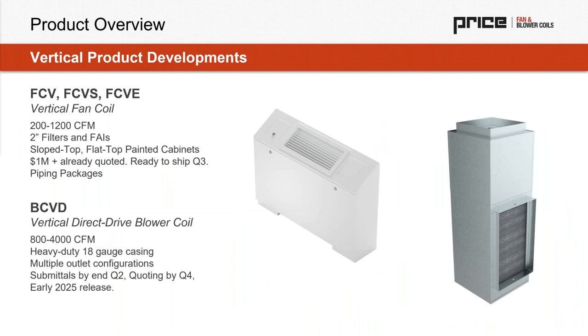So when we look at institutional work and dormitories, and even K through 12 schools, the vertical under-window fan coil is a very popular option. It provides 200 to 1200 CFM and comes in a painted exposed offering, a concealed one that would hide behind some kind of other architectural finish, whether that's drywall or some built-out plenum or mounting location. And then we have the exposed, which is both flat top and slope top, really just stopping occupants from placing potentially books or bags or whatever we'd see, even in dormitories, ideally not installing a hot plate on top of the fan coil. So we see that very frequently used in institutional work.